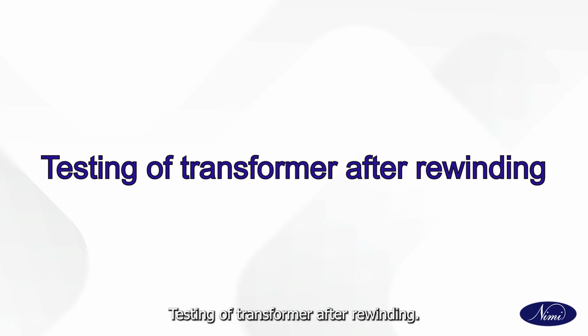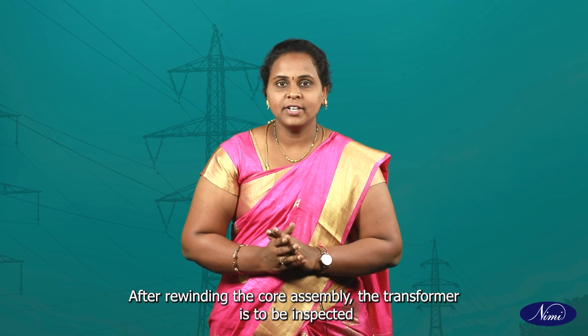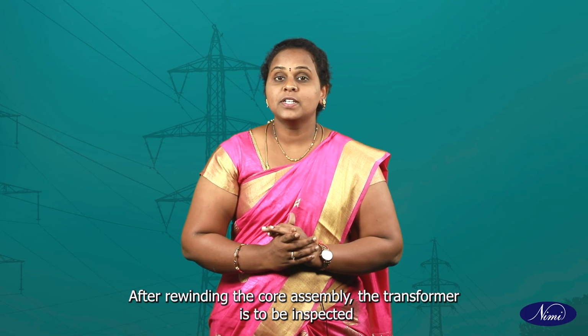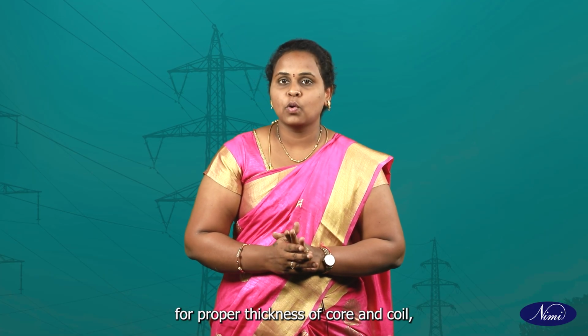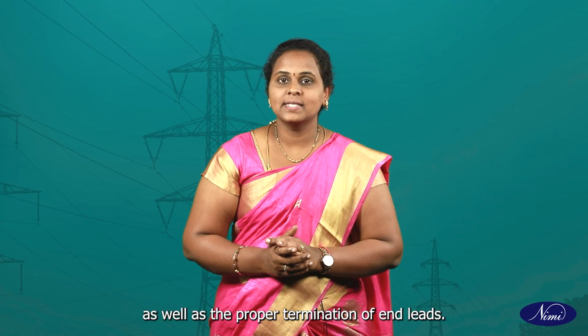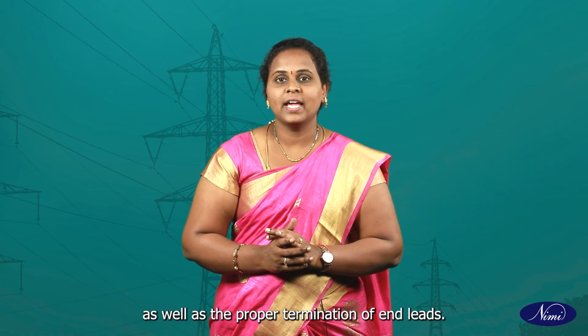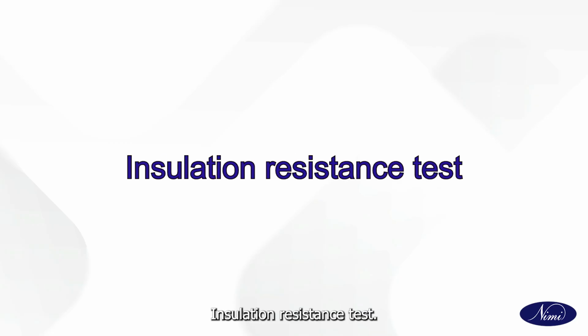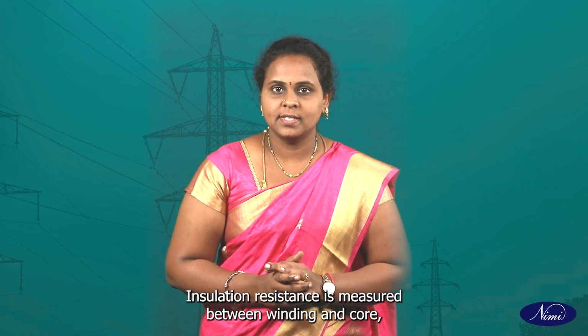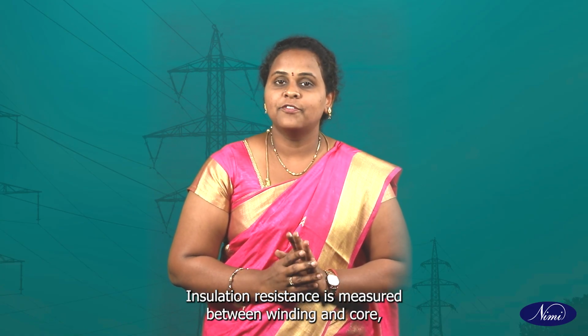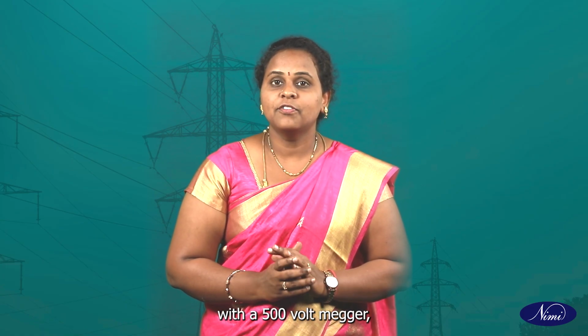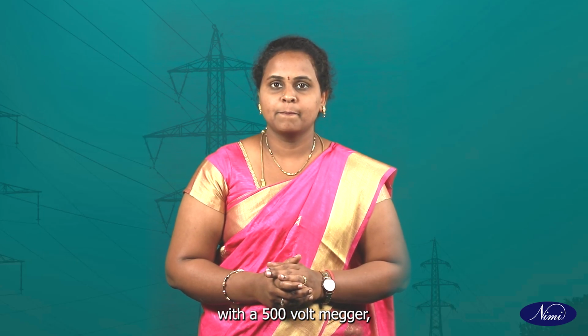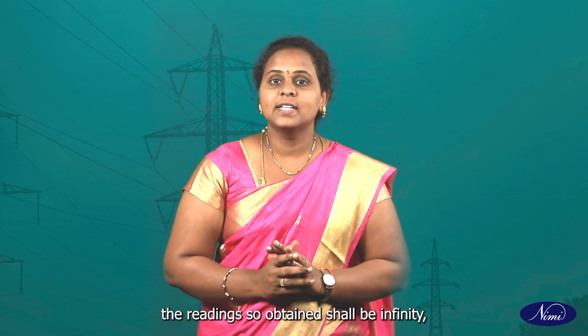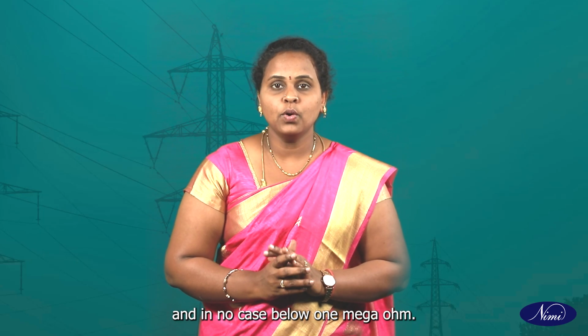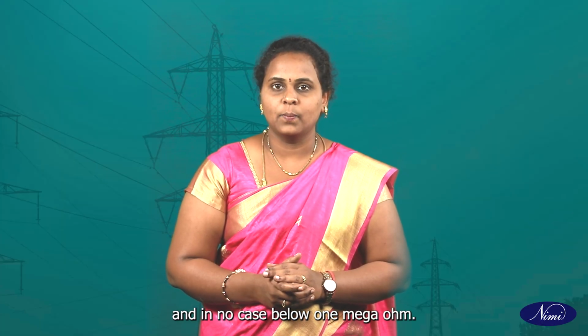Testing of transformer after rewinding. After rewinding the core assembly, the transformer is to be inspected for proper thickness of core and coil as well as the proper termination of end leads. Insulation resistance test. Insulation resistance is measured between winding and core with a 500 volt megger. The reading so obtained shall be infinity and in no case below 1 mega ohm.